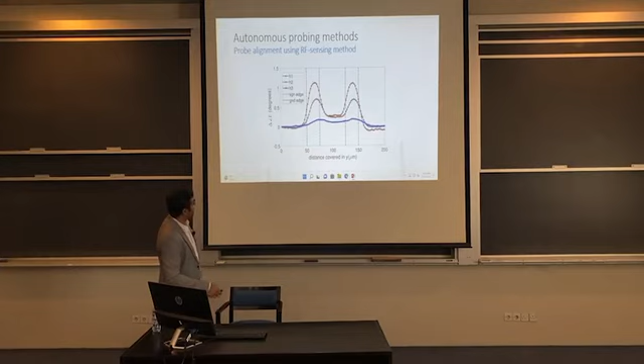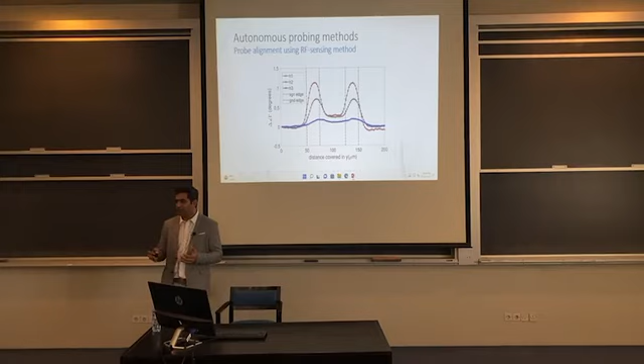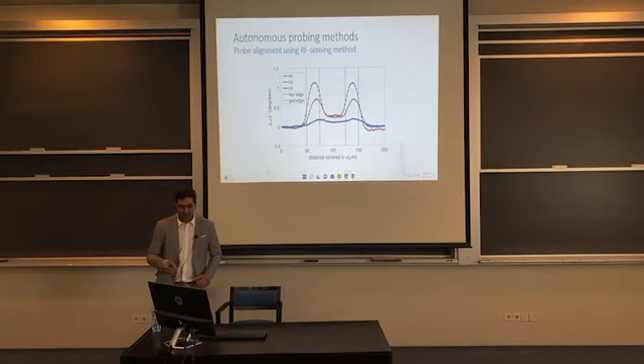Here is a clear sign that the weakest link in your system determines your accuracy. If your microscope is simply not good enough for that kind of resolution, you will have a very high state-of-the-art probing system, but you won't be able to use that accuracy if the camera doesn't support it. This is a paper that we just published a few months ago. Another very interesting way of tracking your probe is by also using the VNA measurements. We found that you can detect the edges on the substrate pretty accurately using this RF sensing. So you combine data: you have a vision system, for example, for scanning your position, but apart from that, you also include data coming from the VNA itself. And this is actually a place where you want to be, because you have information coming in from independent sources, and using machine learning algorithms, you can make even better decisions. That's a domain in itself, to be honest.